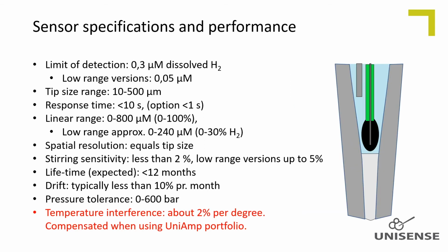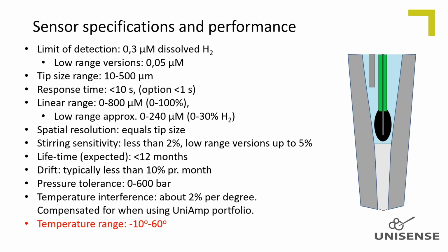In the web lecture about amperometric microsensors, the temperature influence is discussed in detail. And it is explained why temperature compensation is difficult for amperometric microsensors. The temperature interference is about 2% per degree. For sensors used with the new UniAmp portfolio, signal is temperature compensated within a plus/minus 3 degrees Celsius interval. We therefore recommend calibrating hydrogen sensors and measuring at the same or almost the same temperature. The sensors can be used from minus 10 to 60 degrees Celsius. At higher temperatures, the baseline and noise level increase and compromise the sensitivity.